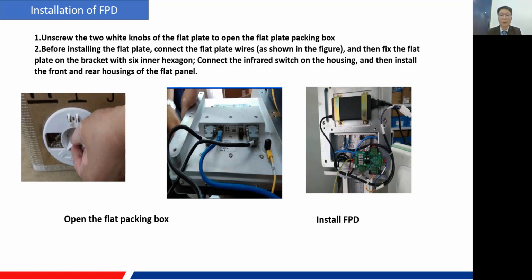Connect the infrared switch on the housing, and then install the front housing of the flat panel detector. Please notice those wires. We need to first connect those wires and then fix the flat panel detector.